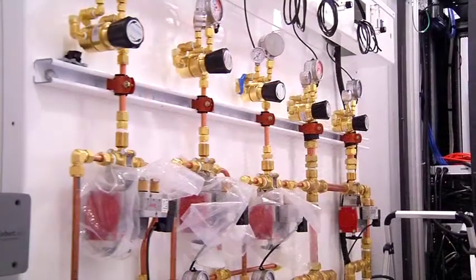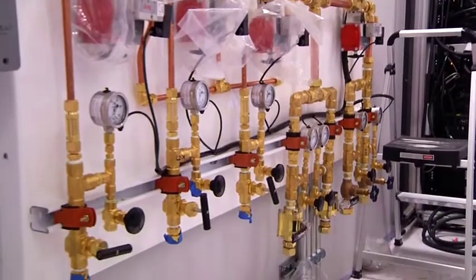Also, in the back of the chamber, there are penetrators for the sanitary system and the firefighting or deluge drain system, and all of those had to be aligned so that, for an industrial construction, these had to be just right. We were very impressed with Kraus-Anderson. They did an excellent job in not only the foundation, but all the interfaces that we have, which is a lot. We have mechanical and electrical and structural interfaces.